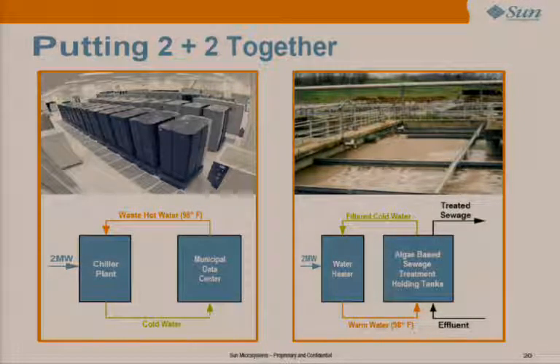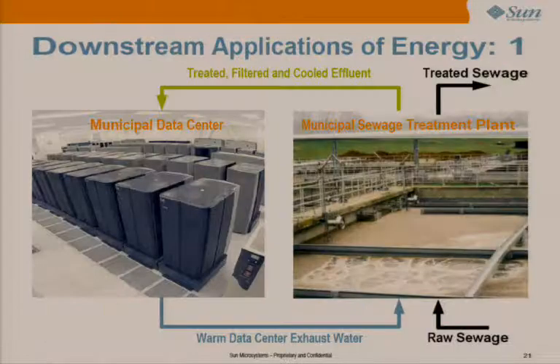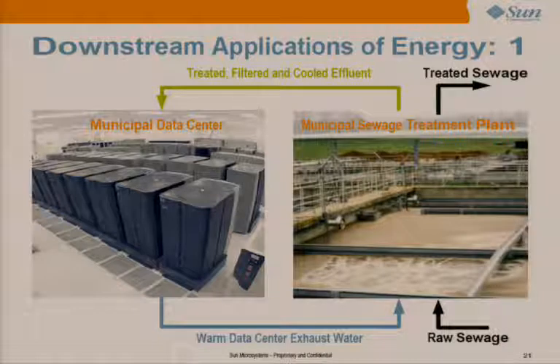Separately, they also had a sewage treatment plant which required algae - it treated sewage through bacterial breakdown, and that needed water at 98 degrees Fahrenheit. So they used to have 2 megawatts of heat coming into a water heater to feed the sewage treatment plant, until some facilities guy in the city had a brainwave: they just used the warm data center exhaust water to feed the algae in the sewage treatment plant, thereby saving the 2 megawatts of electricity.